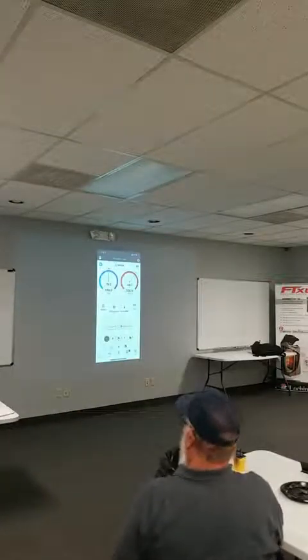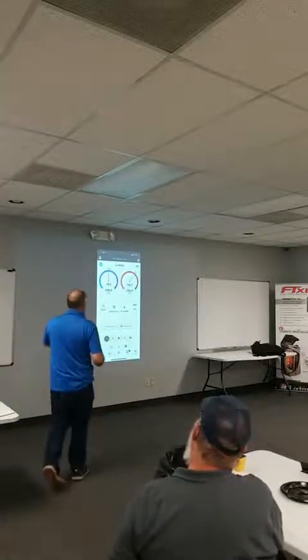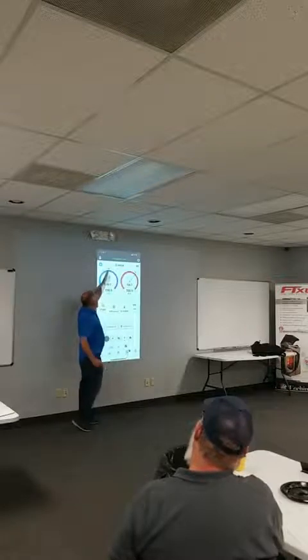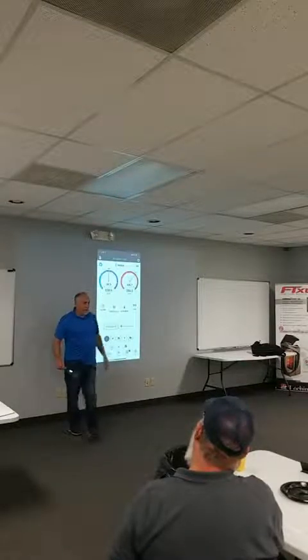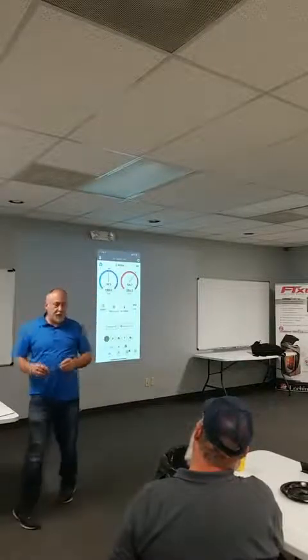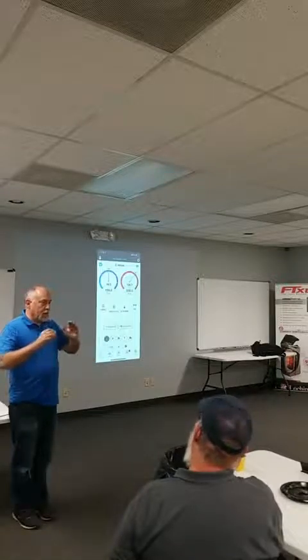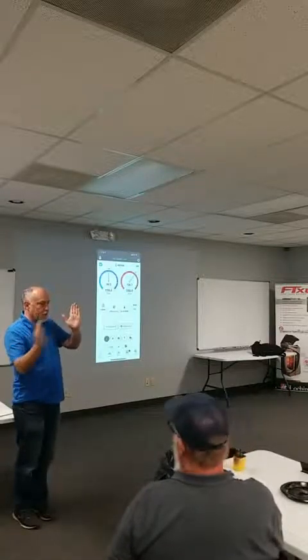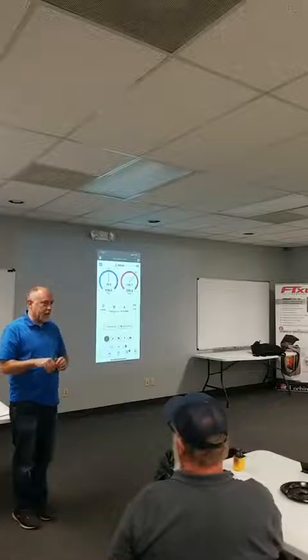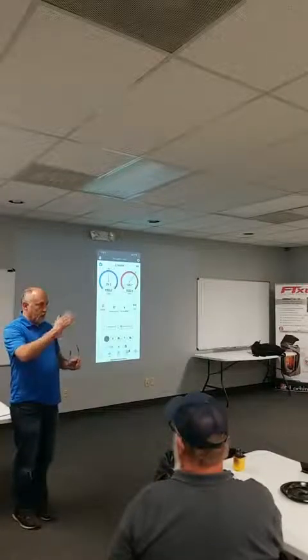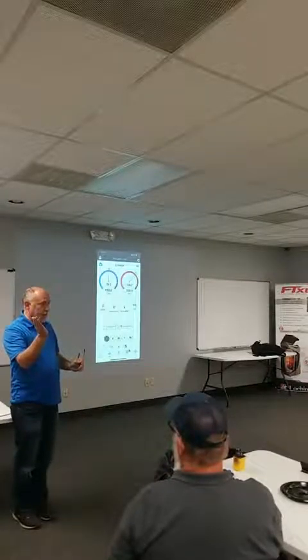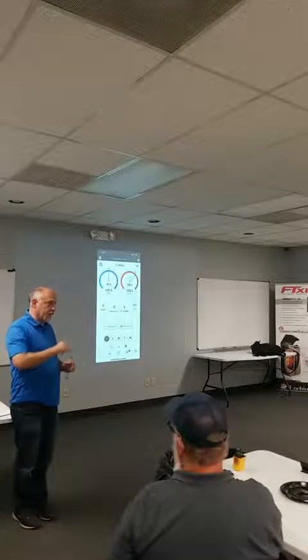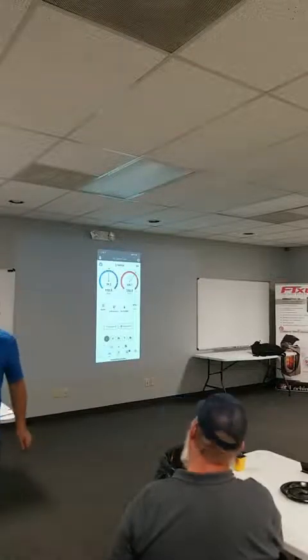The reason also that this target is offset, you notice that this one's sort of centered and this one's offset, is that this is allowable also for latent capacity increase. If you were to blow air on the probe, you'll actually see that latent zone increase, because it's showing you that it's allowed to go into that range. It'll be higher than normal, but when it gets back into the 70-degree range, things will be more in range.